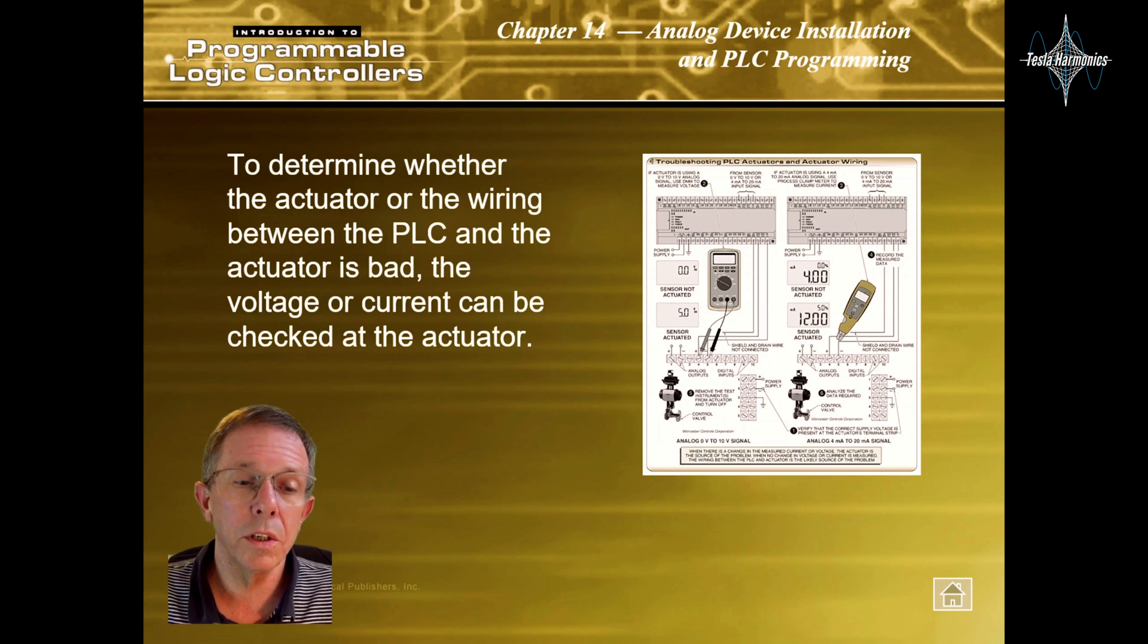To determine whether the actuator or wiring between the PLC and the actuator is bad, the voltage or current can be checked at the actuator.